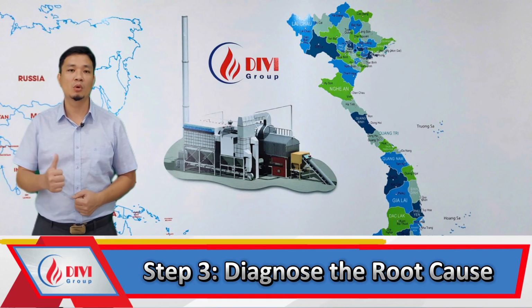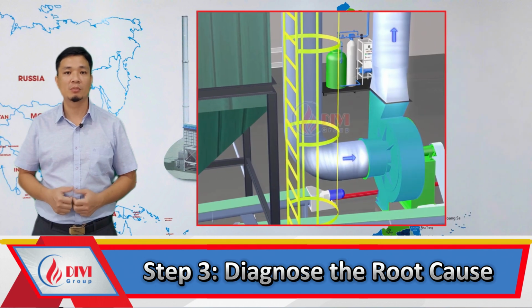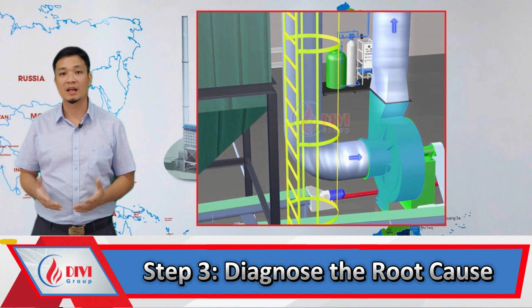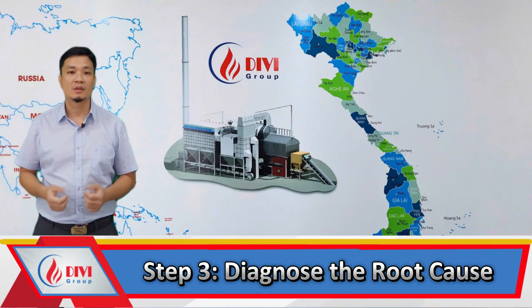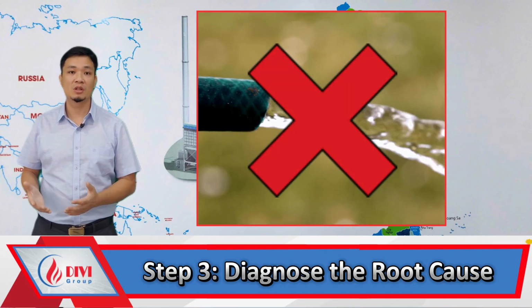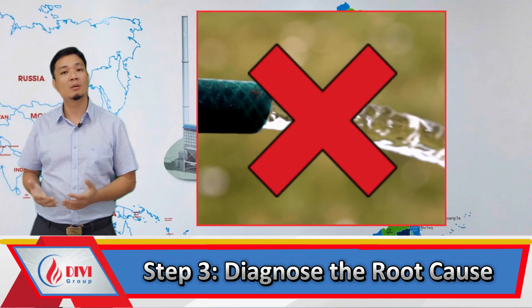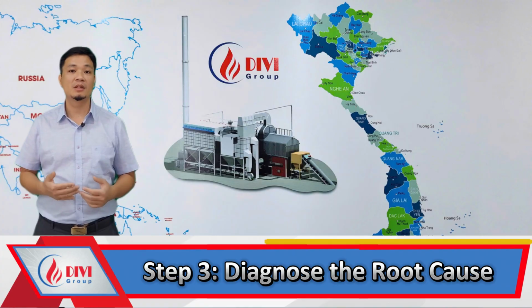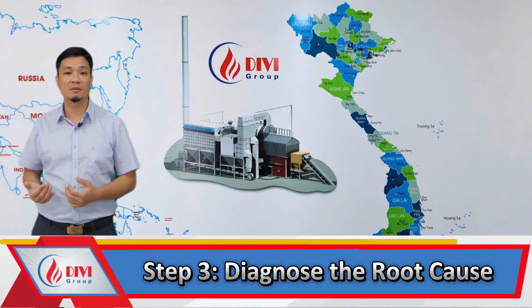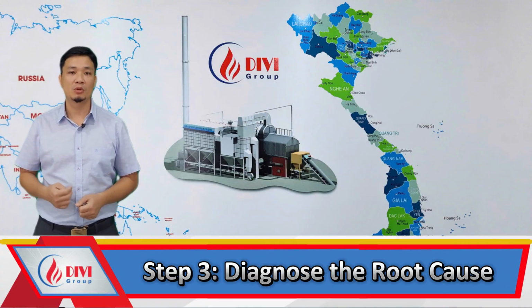After ensuring that the boiler is fully depressurized, you may use the induced draft or ID fan to accelerate cooling. However, never use cold water spray or directly introduce water into the boiler to cool it down. This is strictly prohibited, as it may cause thermal shock or tube explosion.